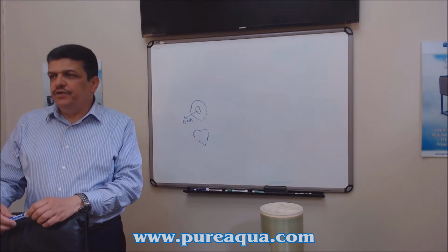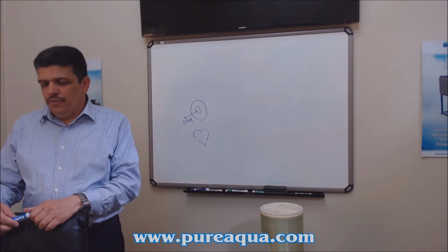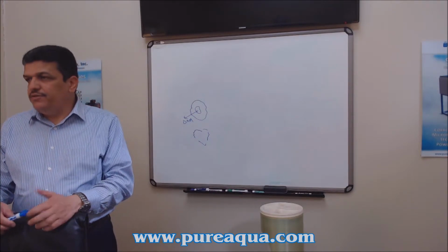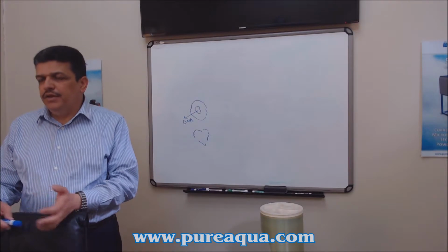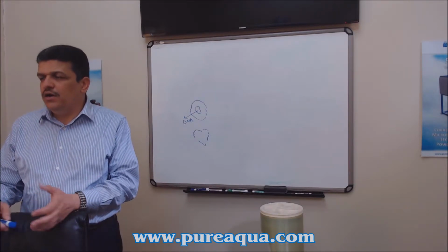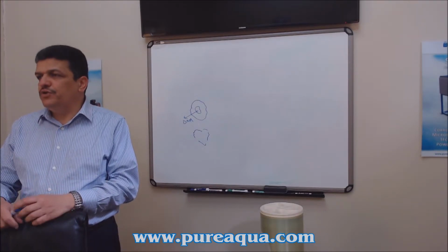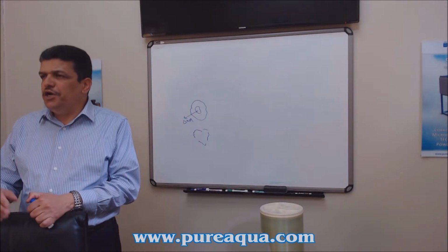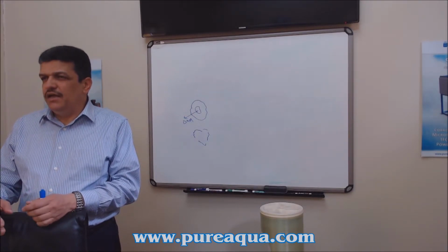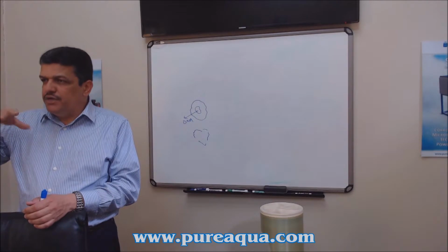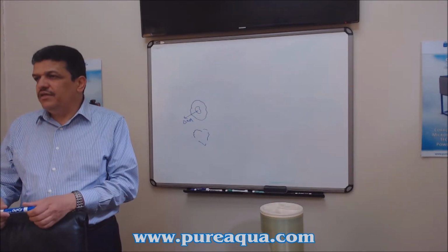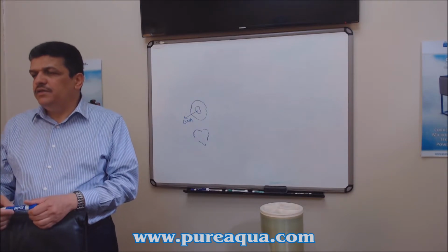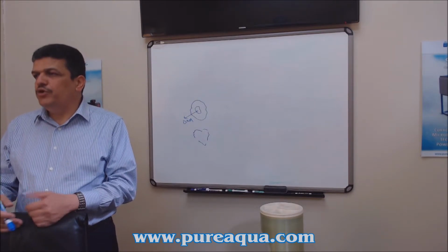The UV can be used for drinking water, for sterilizing milk, juices, wastewater. It depends on how strong the intensity is. The more turbid the water is, the harder it is for the light to penetrate; it's easier for the UV to disinfect clear water. We may have to go for higher intensity if the water is becoming more turbid.